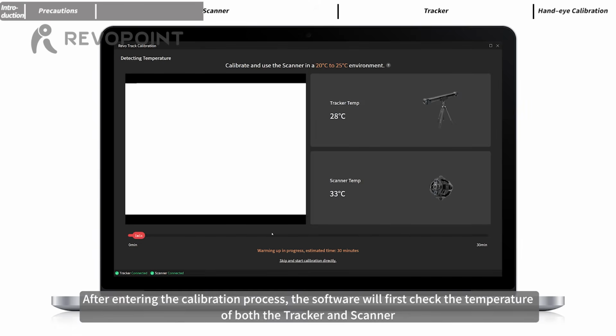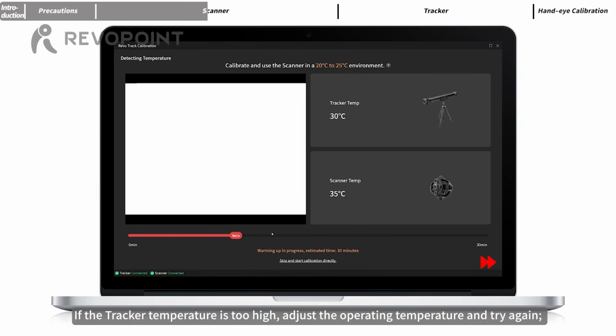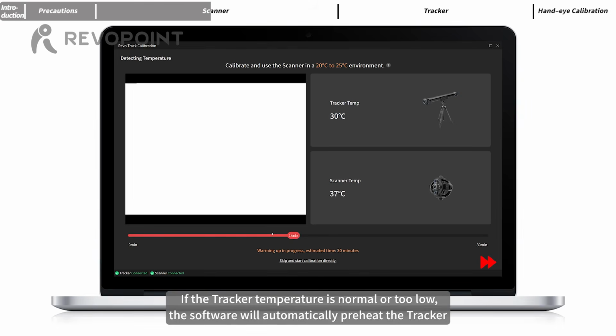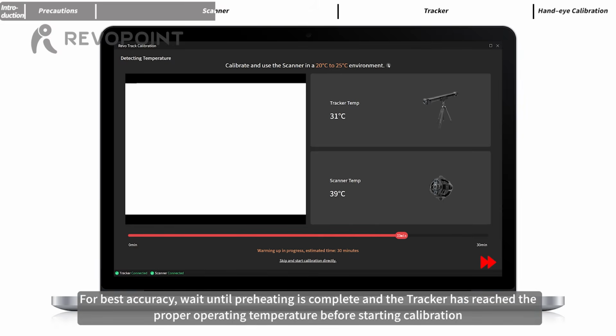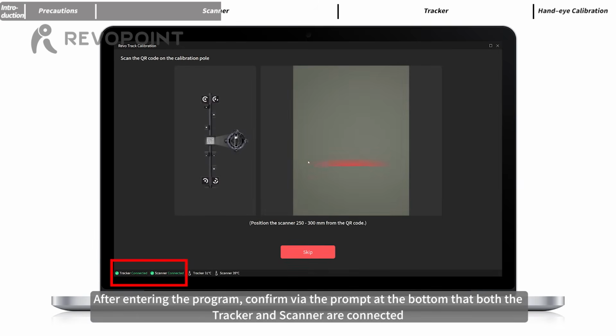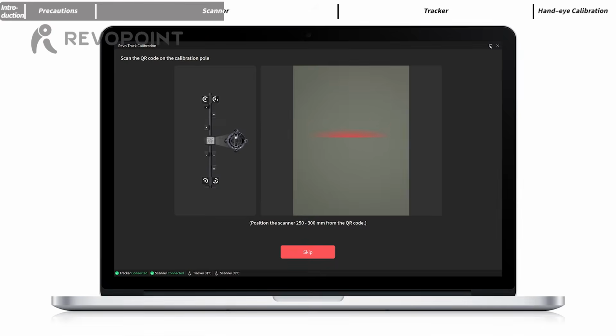After entering the calibration process, the software will first check the temperature of both the tracker and scanner. If the tracker temperature is too high, adjust the operating temperature and try again. If the tracker temperature is normal or too low, the software will automatically preheat the tracker. For best accuracy, wait until preheating is complete and the tracker has reached the proper operating temperature before starting calibration. After entering the program, confirm via the prompt at the bottom that both the tracker and scanner are connected.